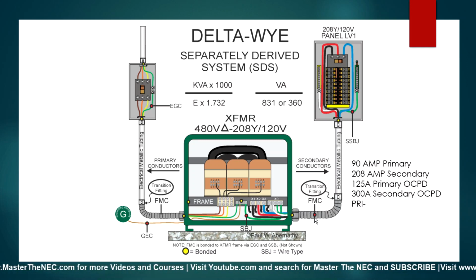For one, it's larger than 1.25 inches, but secondly, we know for a fact that the conductors in it are terminated on devices that are larger than 20 amps. So it is permitted to be an equipment grounding conductor under 250.118 where it is 20 amps or less protecting the conductors inside of it. Well, that's not our case here. So we don't have to do anything with that part of it.